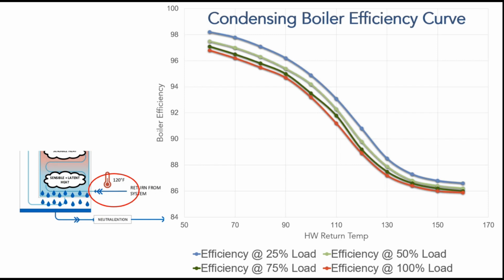So this is a generic condensing boiler efficiency curve. On your y-axis here, you have your boiler efficiency. On your x-axis, you have your hot water return temperature. So this return temperature is what's going to drive whether or not your boiler can get into condensing mode. The different lines are different loads, so the boiler's efficiency at 25%, 50%, etc., at each of these hot water return temperatures. The takeaway here is you have to get that hot water return temperature down below 130, 135 to really get into condensing mode, and then you'll quickly increase the efficiency of your boiler.